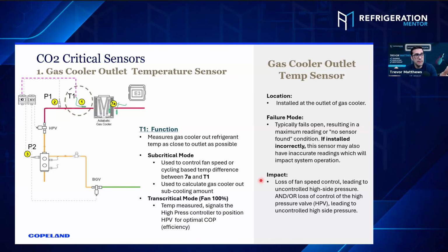I saw one in a training maybe 2 months ago where they actually put the drop leg sensor inside the building at the rack with an insulation that just fell right off. He just took a picture. He's like, Trevor, look at this. And it was with zip ties. So inside, not outside, where it can get -20, on the inside of the building. You can run into a lot of issues because you're not actually checking what the subcooling is at the gas cooler or the condenser. You're checking the subcooling inside the building 40 feet away, 50 feet away from the gas cooler. That'll cause a lot of havoc on yourself.